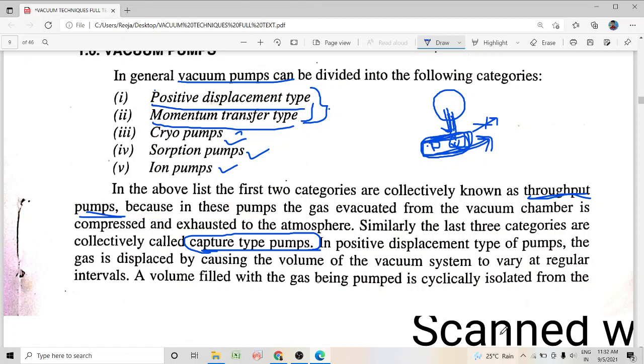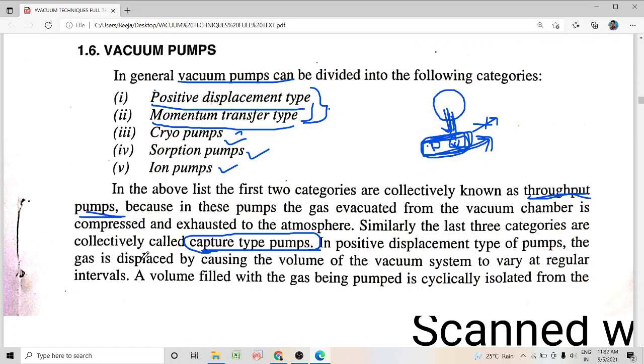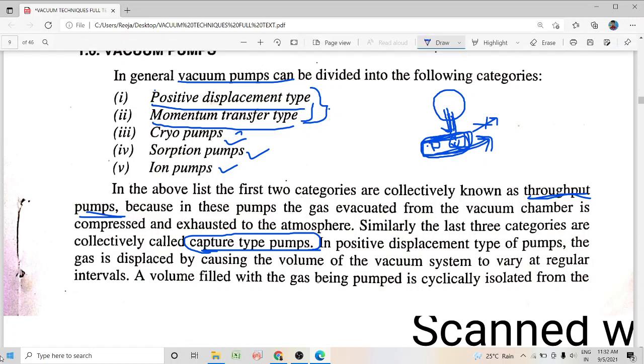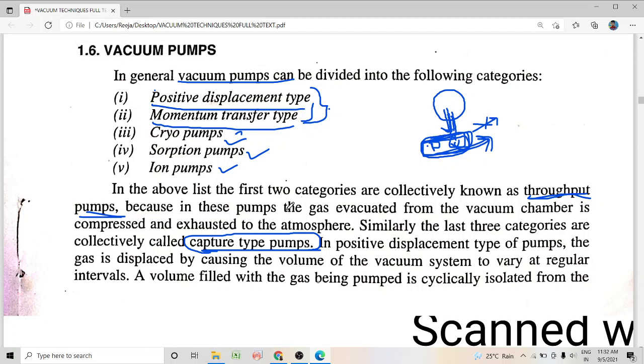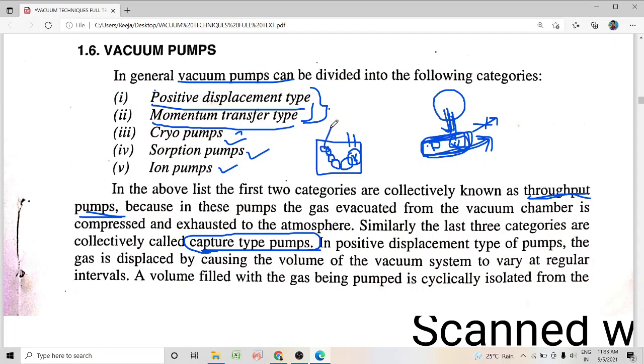In a positive displacement type pump, the gas which has been extracted from the vacuum vessel undergoes a change in volume during regular intervals of time and is finally pushed out of the pump. Inside the pump, you have taken in some amount of gas from the chamber, its volume keeps on changing — it undergoes some kind of compression — its volume goes on decreasing, it gets compressed, and finally it is exhausted out of the vacuum pump.